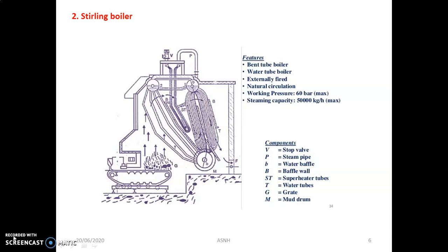The second important water tube boiler is the Stirling boiler. It consists of three drums: two upper drums and one drum located at the bottom. The bottom drum is the water or mud drum, while the upper two drums are the steam drums. The steam drums are connected to the mud drum by banks of bent tubes. The steam and water space of the steam drums are interconnected so that a balance of water and steam may be obtained.